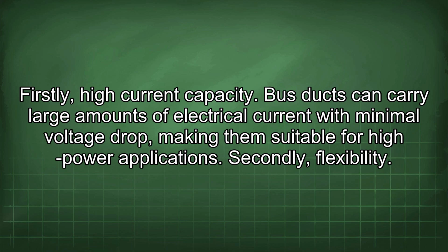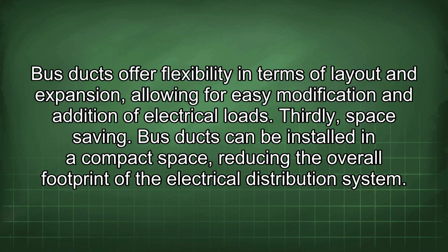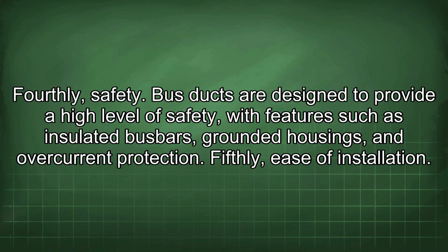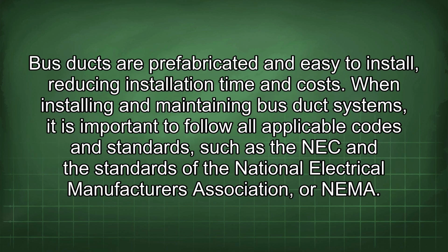Secondly, flexibility. Bus ducts offer flexibility in terms of layout and expansion, allowing for easy modification and addition of electrical loads. Thirdly, space saving. Bus ducts can be installed in a compact space, reducing the overall footprint of the electrical distribution system. Fourthly, safety. Bus ducts are designed to provide a high level of safety, with features such as insulated bus bars, grounded housings, and overcurrent protection. Fifthly, ease of installation. Bus ducts are prefabricated and easy to install, reducing installation time and costs.